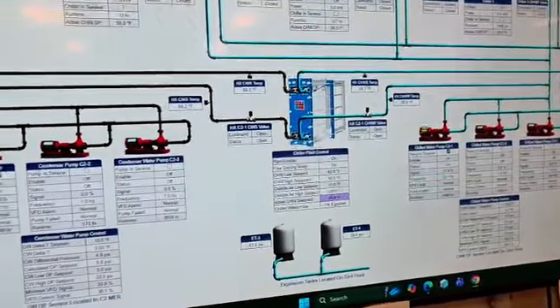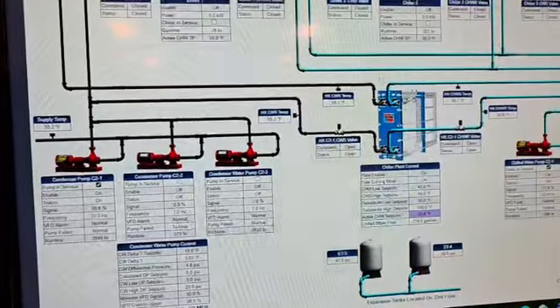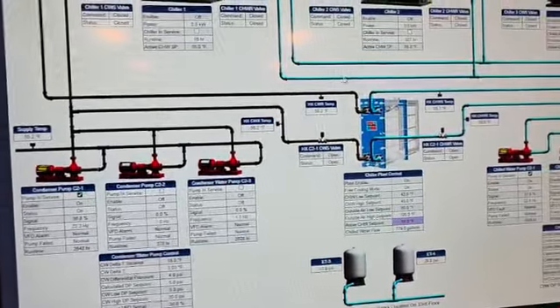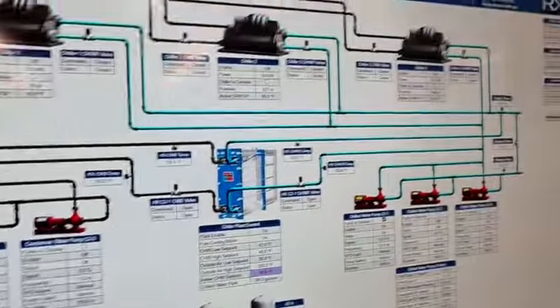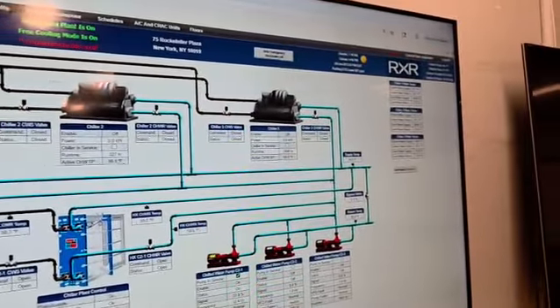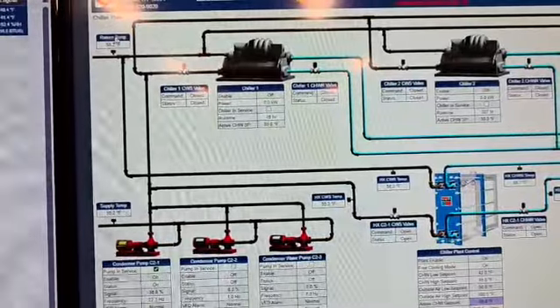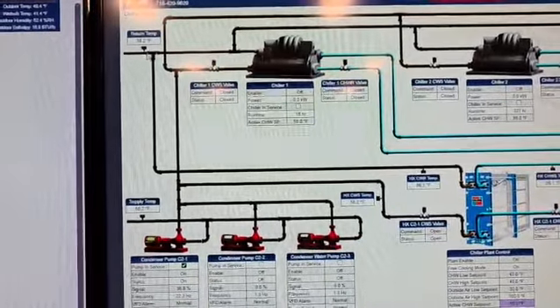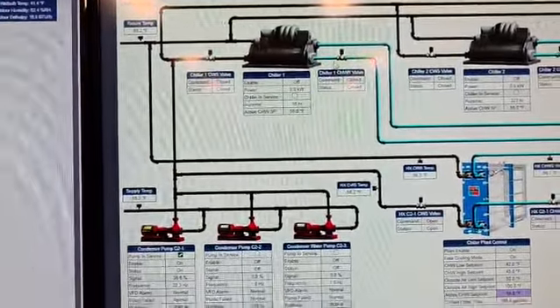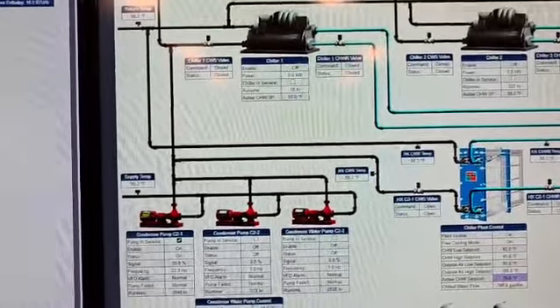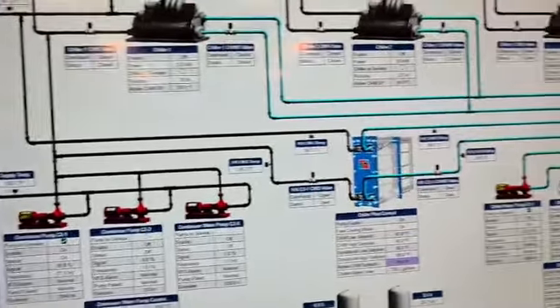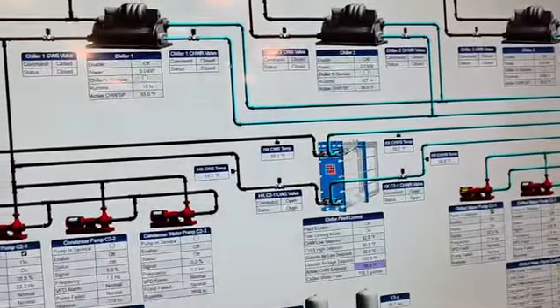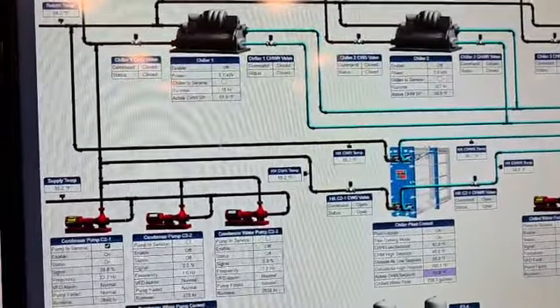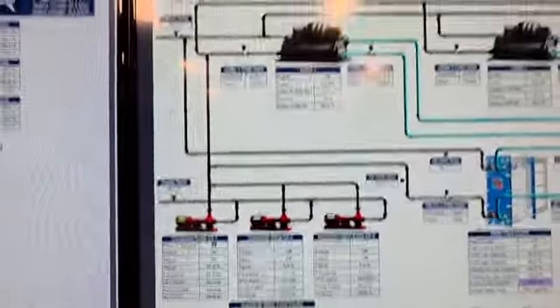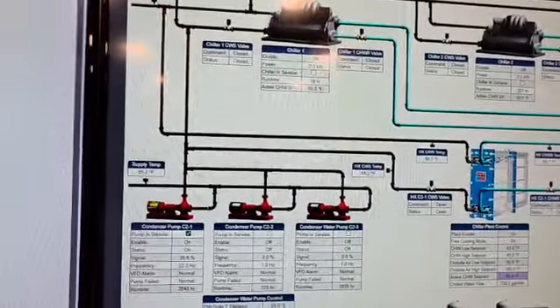Now you have this thing in here, which is called free cooling, right? That's during the time when you are between seasons. Sometimes the cooling tower cools the water cold enough that you could cool your building with the water without using the compressors. You see the compressors now are off. You don't need them because the cooling tower water is cold enough to cool the building.